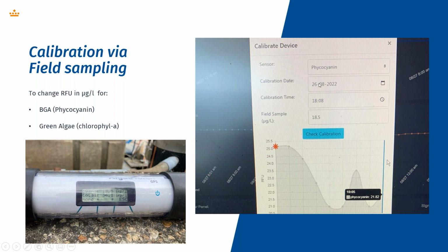You can enter the calibration date, calibration time, and also the result of your field sample. After filling in, you can push the blue button, check calibration. At that time, all the measurements will be converted to microgram per liter. So you measure in RFU, and then you get a transformation into microgram per liter. And as shown in the picture in the left corner, the cyanobacteria were 18.5 microgram per liter, which I put into the program in the web portal.